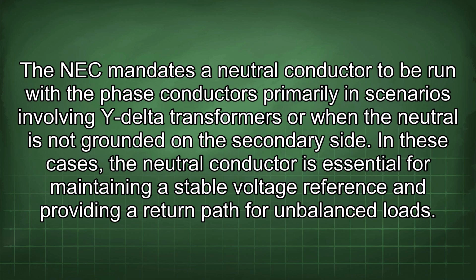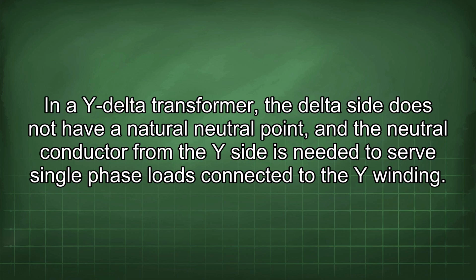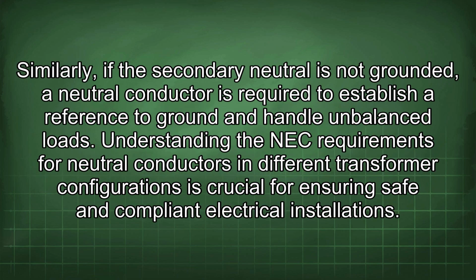In these cases, the neutral conductor is essential for maintaining a stable voltage reference and providing a return path for unbalanced loads. In a Y-delta transformer, the delta side does not have a natural neutral point, and the neutral conductor from the Y side is needed to serve single-phase loads connected to the Y winding. Similarly, if the secondary neutral is not grounded, a neutral conductor is required to establish a reference to ground and handle unbalanced loads.